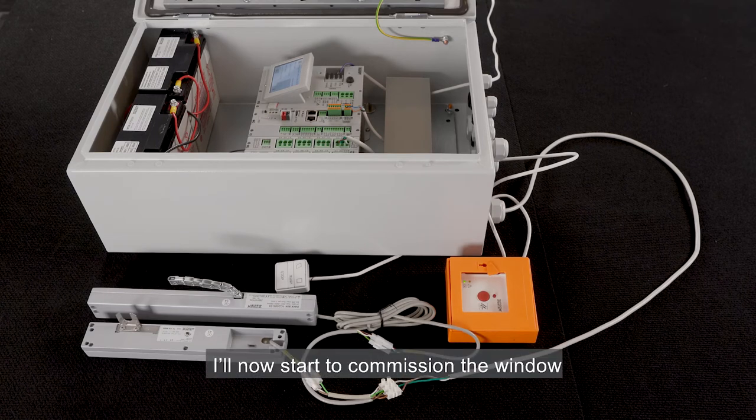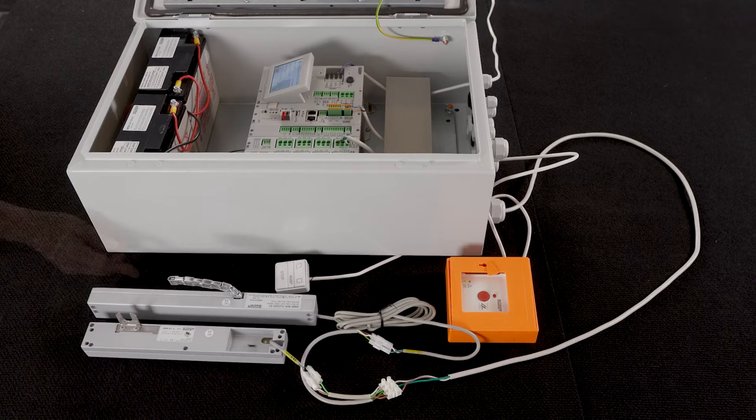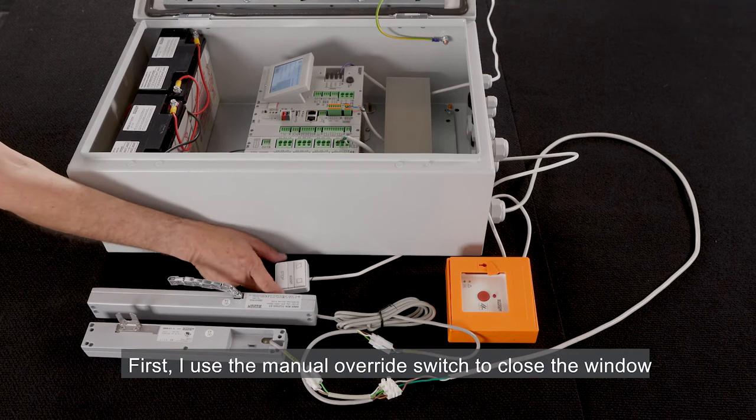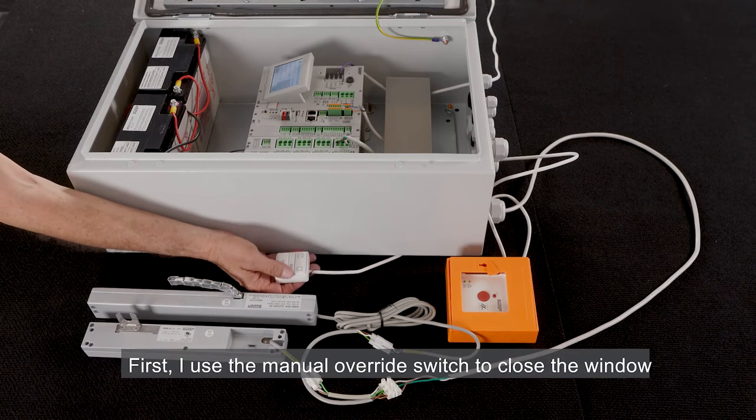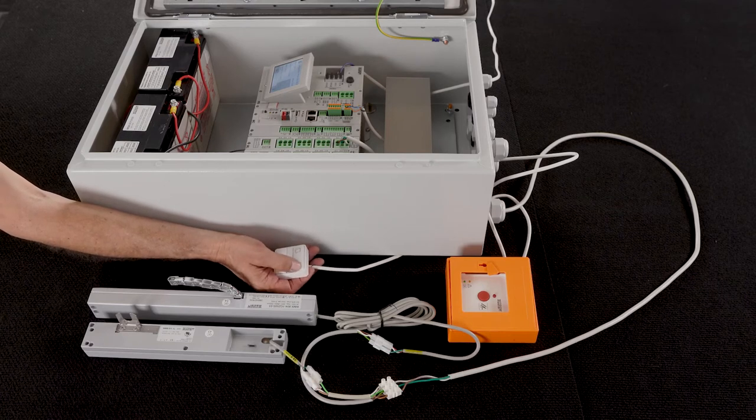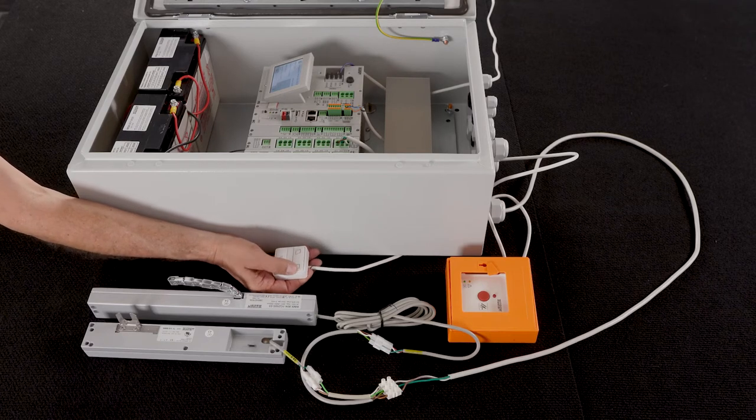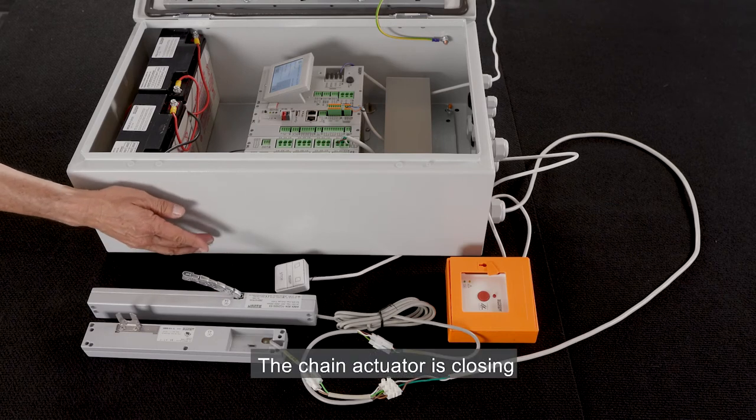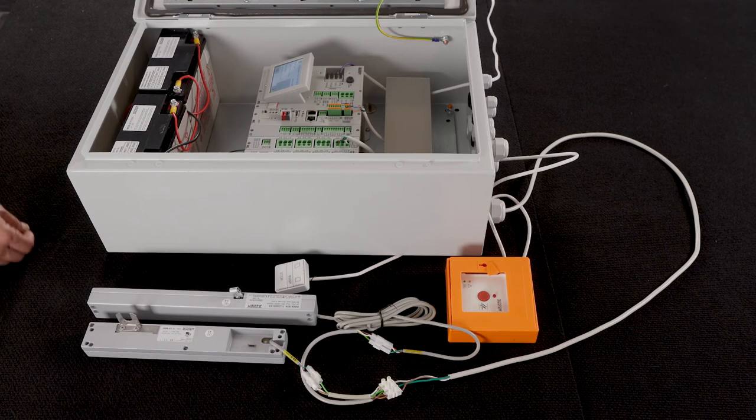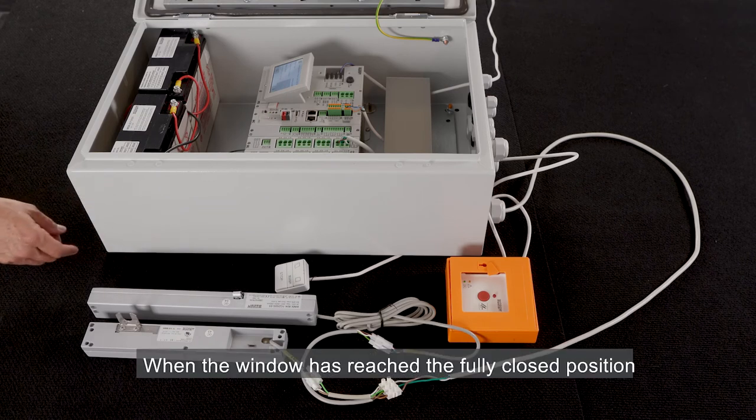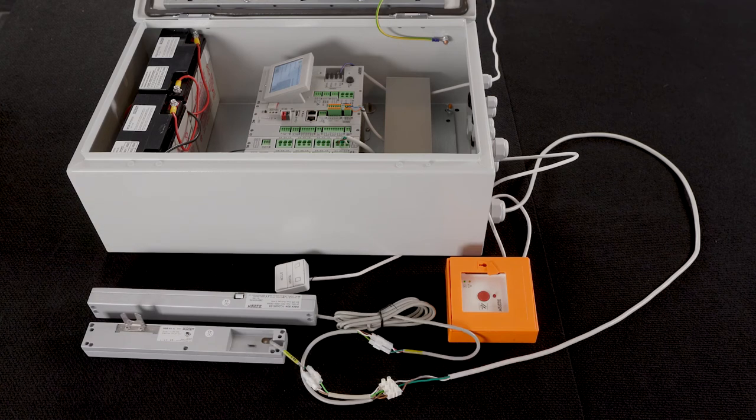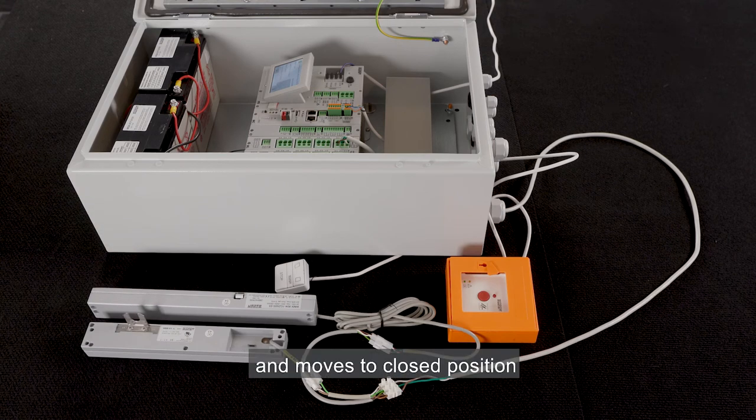I'll now start to commission the window. The window is now slightly open. First I use the manual override switch to close the window. I press the close button. The chain actuator is closing. When the window has reached the fully closed position, the locking actuator begins to run and moves to closed position.